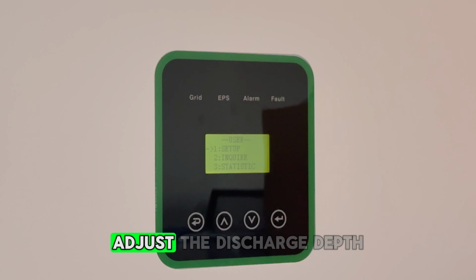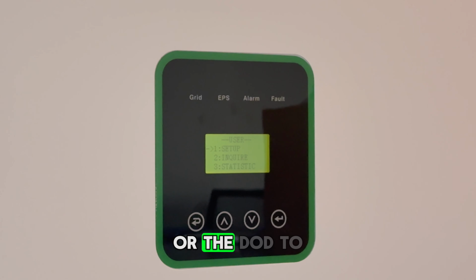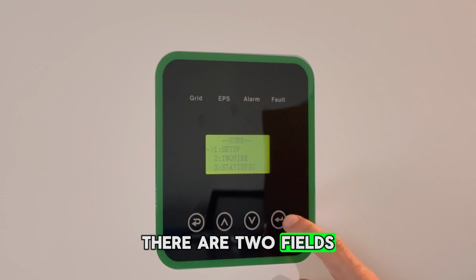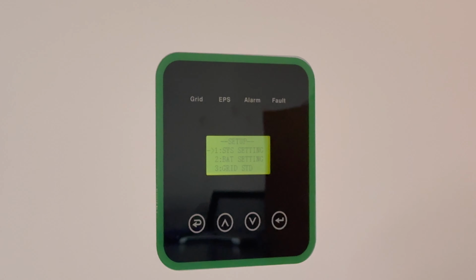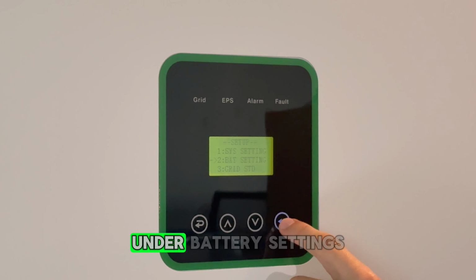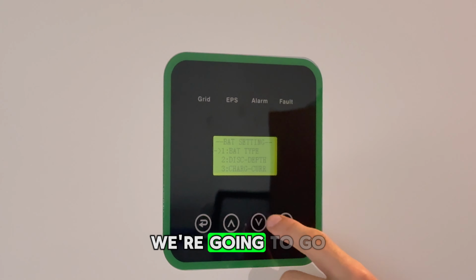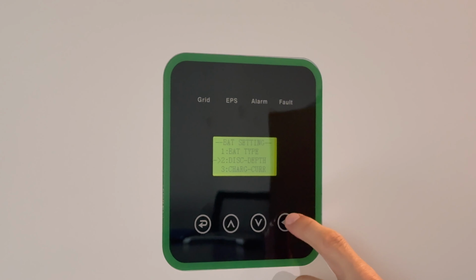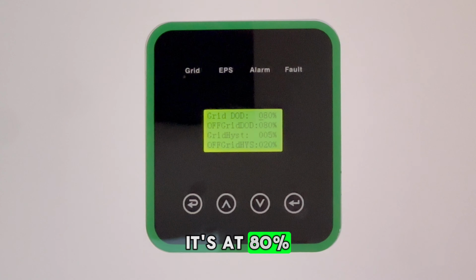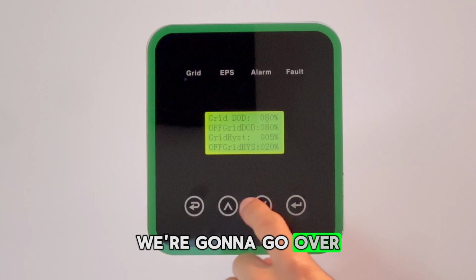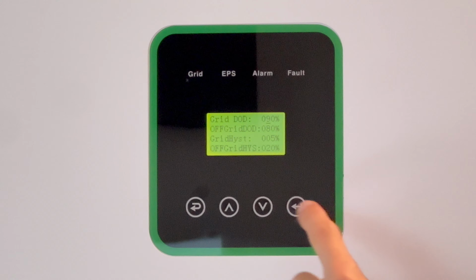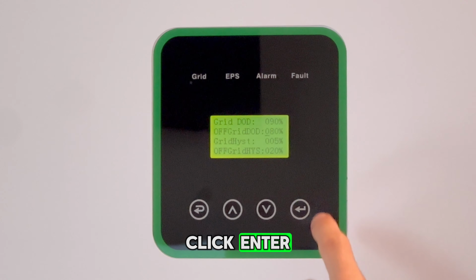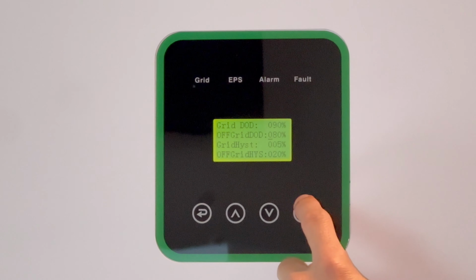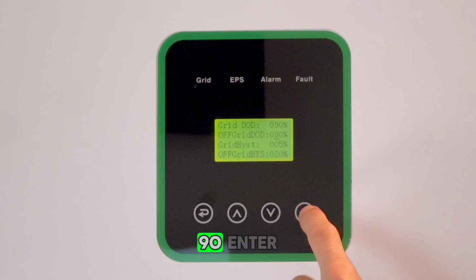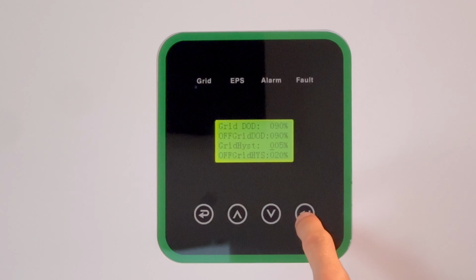Next, we're going to adjust the discharge depth, or the DOD, to 90%. There are 2 fields. We're going to go into setup. We're going to go down to number 2 under battery settings. We're going to go to number 2, which is the discharge depth. We're going to see that it's at 80%. We're going to go over, bring it up to 90. Click enter. 90, enter.